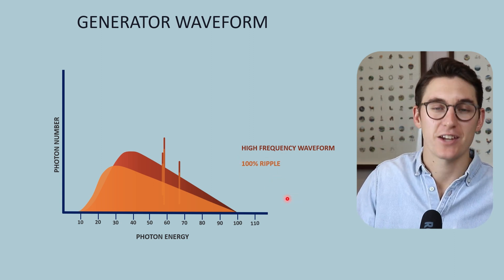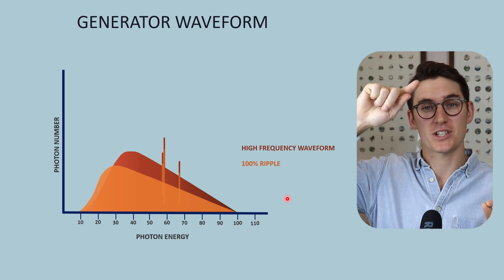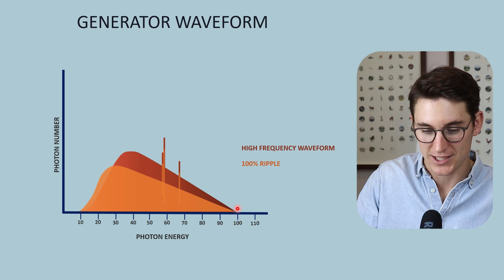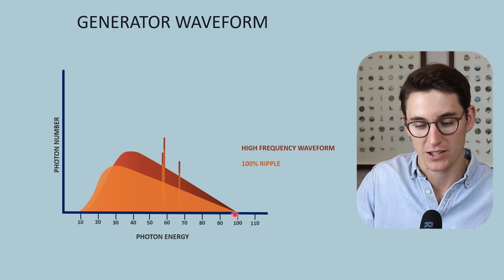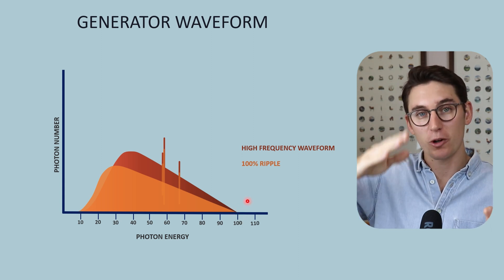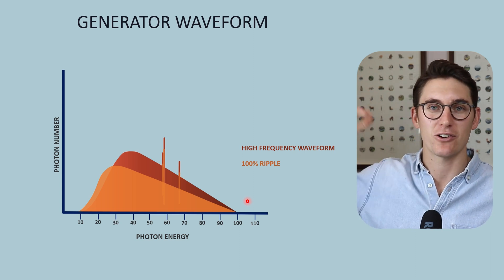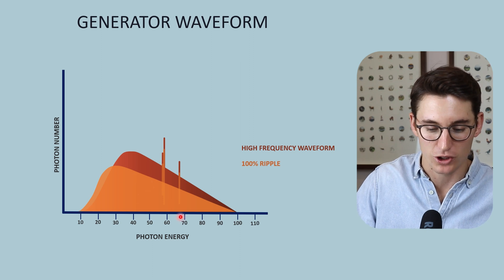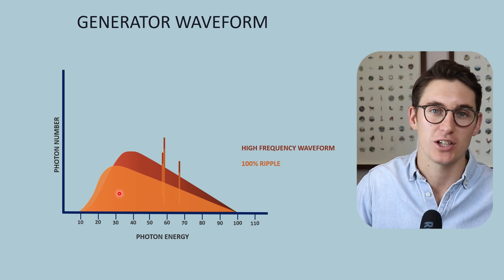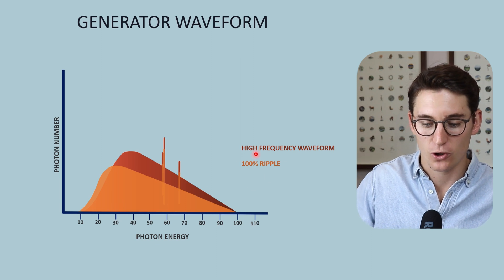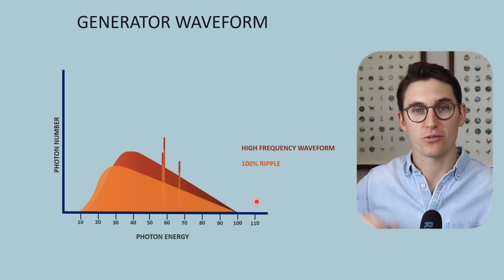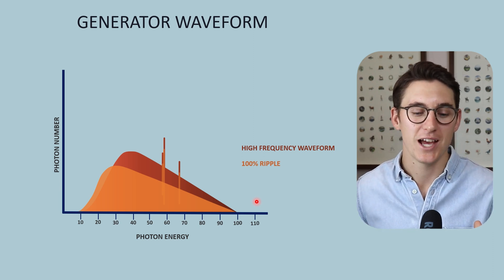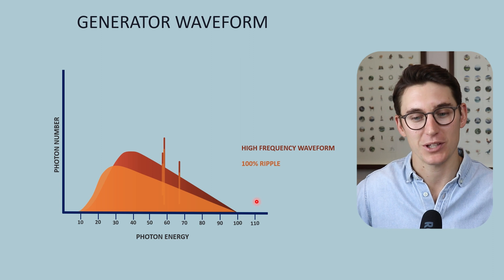When we have a 100% ripple waveform, there are periods of time where our KVP will reach a peak — that's why we have photon energies at the maximum, say 100 keV in this example. But there are long periods of time when our voltage is lower than our KVP, resulting in fewer photons as well as a reduction in the average energy of those photons. So more ripple results in fewer x-rays and lower energy x-rays — a reduction in both x-ray beam quantity and x-ray beam quality.